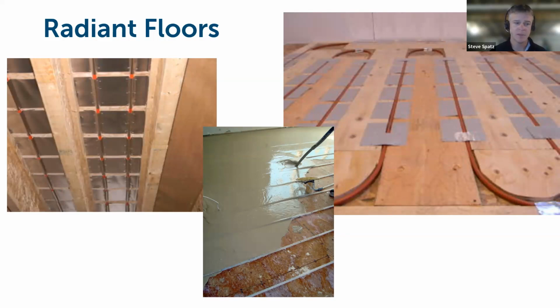So these are systems that are meant to run at steady state. That's a good match for heat pump equipment as well. We're talking about steady state efficiency here, so there's not huge swings in temperature in the room or in the space or in the fluid medium running through the piping. We're keeping a more uniform temperature and uniform circulation going with these types of distribution options. There are, again, as I'm illustrating here, different ways of doing radiant floors. And over the years, I think there's not a huge impact on overall performance by differences in the type of radiant floor we're talking about here. Whether it's in the subfloor, below the subfloor, gypcrete, you can get similar levels of efficacy and performance across the different types and different ways of achieving a radiant system.